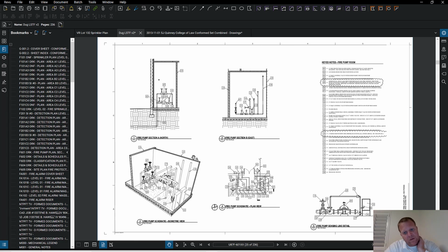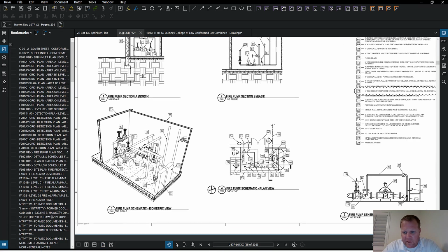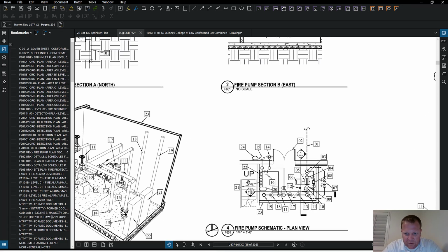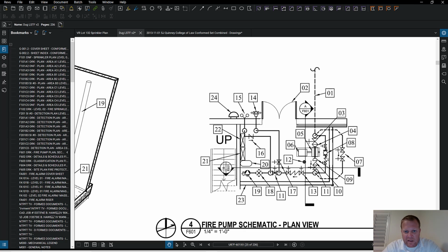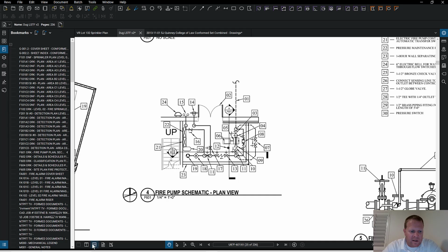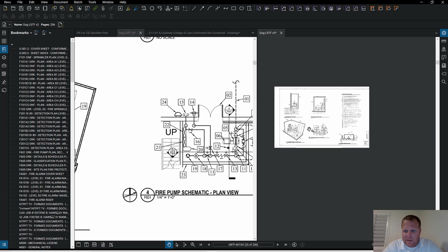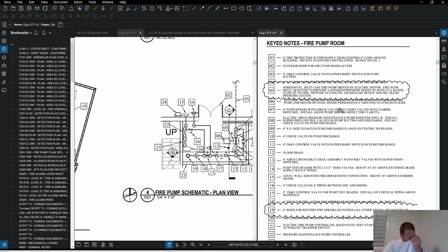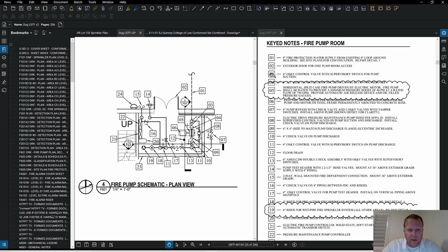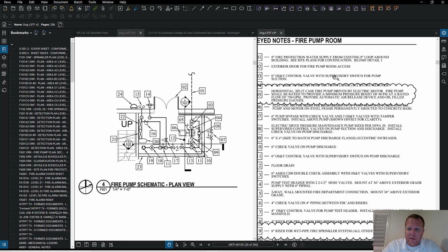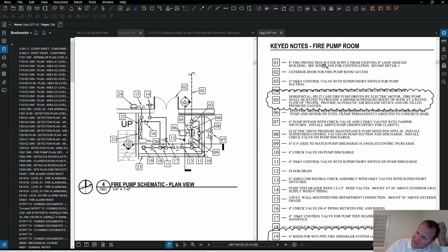All right. We've used the word riser quite a bit, so let's just look at this for a second. Fire pump schematic. You guys should know what a schematic is now, and then we can read through all of this. Okay, number one, we have the 8-inch fire protection water from the existing 8-inch loop around the building. So there's an 8-inch water line going around the building, and that is providing the volume of water needed for the building suppression system. Kind of cool. Instead of building a tank, sometimes they'll loop the building with a larger water line, and that'll work.